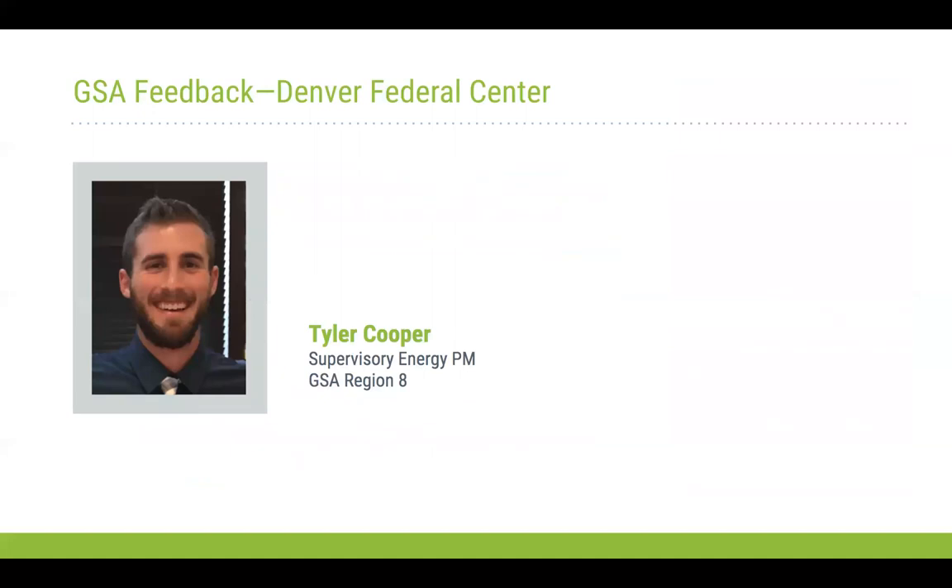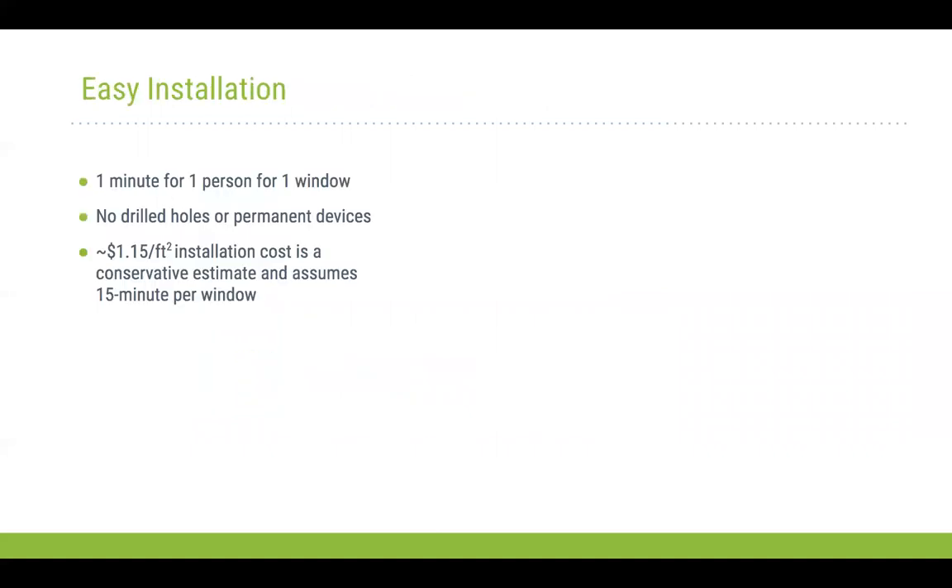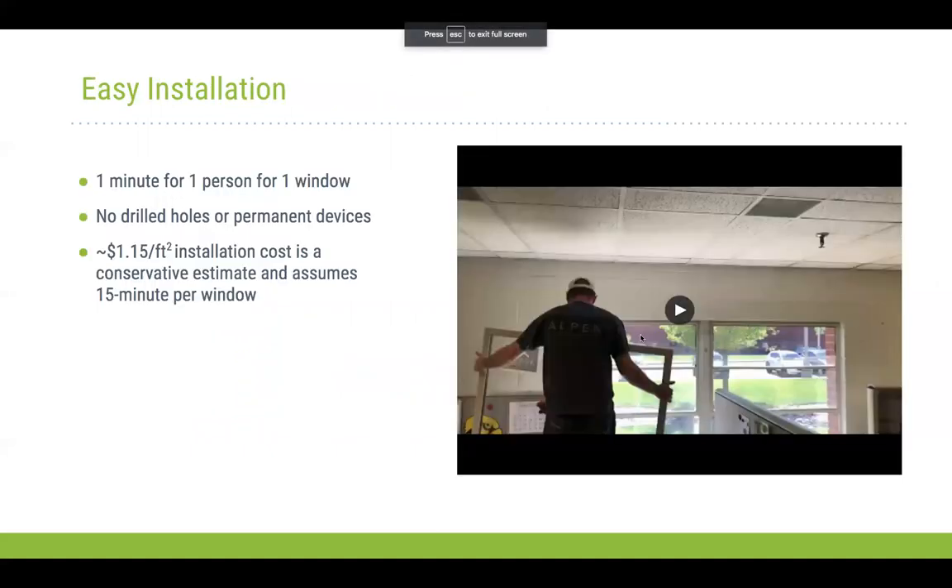I'm Tyler Cooper, mechanical engineer in Region 8 for GSA. I'm going to go over on-the-ground feedback, general installation of the window inserts, and feedback from occupants. The big thing with these is the easy installation process. Assuming everything is sized correctly, we estimate about one minute per person for one window to install. Conservatively we estimate about $1.15 per square foot on installation cost, assuming 15 minutes per window for cost-estimating purposes. There are no drilled holes or permanent devices needed to fix the windows.